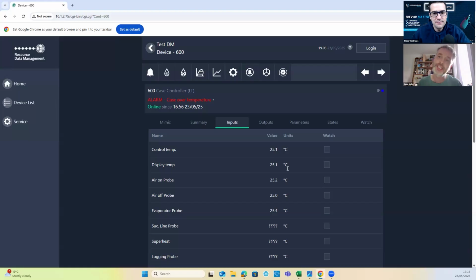They're all saying virtually the same, which also is good news to me, because if I've got 3 saying 25 and 1 saying 35, I'm saying they're all in a room together. Why is one much higher than the other? I also noticed from that, I've got a suction line probe fault, right? And the controller's flashing PRB4 on the front, telling me it's a probe 4 fault.